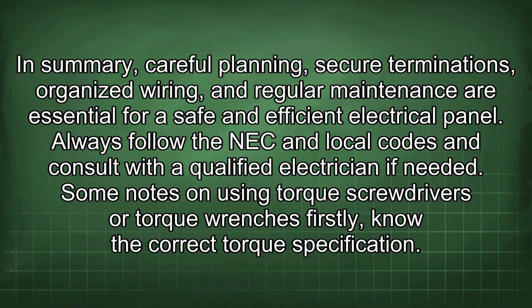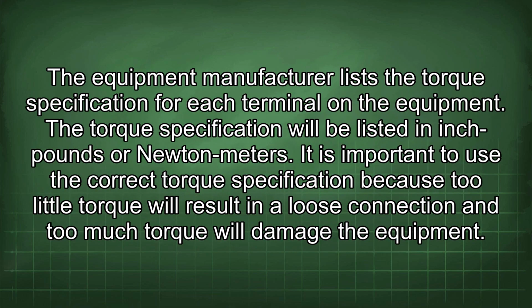Some notes on using torque screwdrivers or torque wrenches. Firstly, know the correct torque specification. The equipment manufacturer lists the torque specification for each terminal on the equipment. The torque specification will be listed in inch-pounds or Newton meters. It is important to use the correct torque specification because too little torque will result in a loose connection and too much torque will damage the equipment.